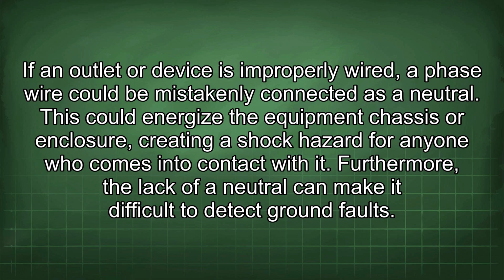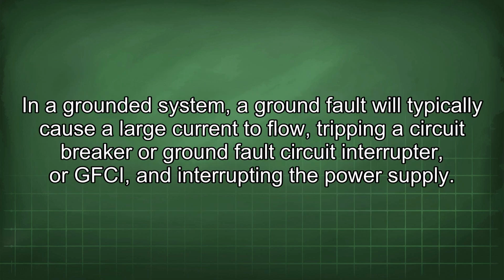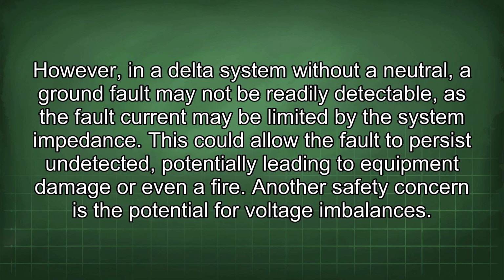Furthermore, the lack of a neutral can make it difficult to detect ground faults. In a grounded system, a ground fault will typically cause a large current to flow, tripping a circuit breaker or ground fault circuit interrupter, or GFCI, and interrupting the power supply. However, in a delta system without a neutral, a ground fault may not be readily detectable, as the fault current may be limited by the system impedance. This could allow the fault to persist undetected, potentially leading to equipment damage or even a fire.